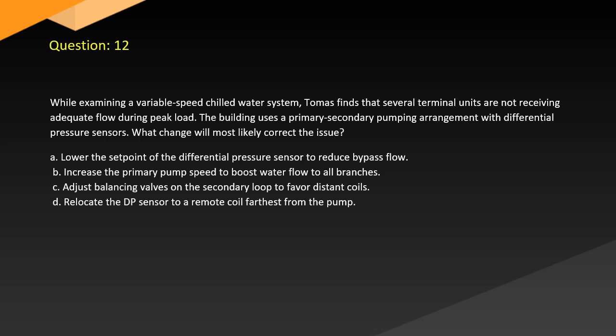Question 12. While examining a variable speed chilled water system, Tomas finds that several terminal units are not receiving adequate flow during peak load. The building uses a primary-secondary pumping arrangement with differential pressure sensors. What change will most likely correct the issue? A. Lower the set point of the differential pressure sensor to reduce bypass flow. B. Increase the primary pump speed to boost water flow to all branches. C. Adjust balancing valves on the secondary loop to favor distant coils. D. Relocate the DP sensor to a remote coil farthest from the pump.